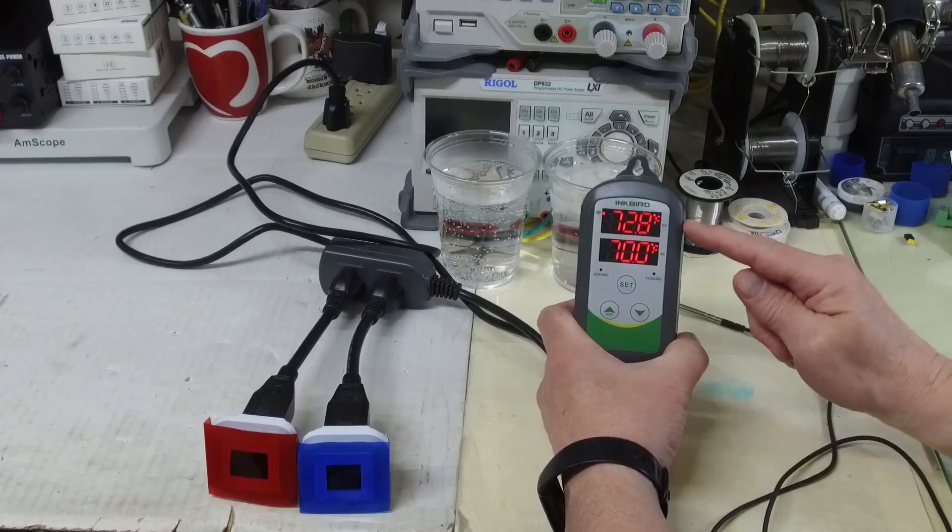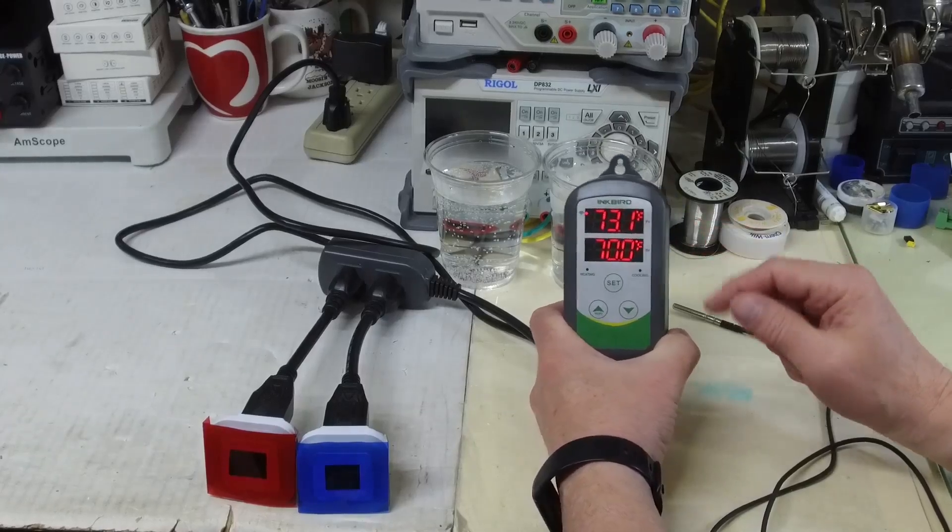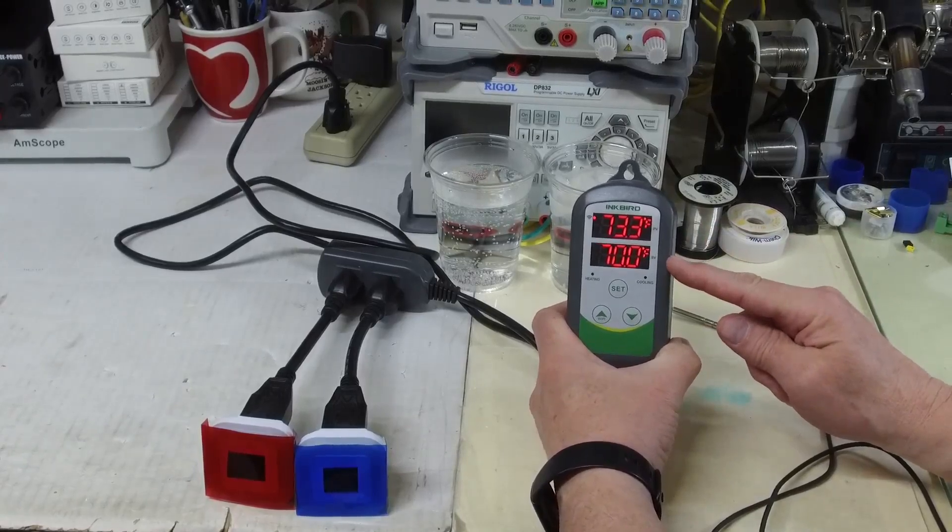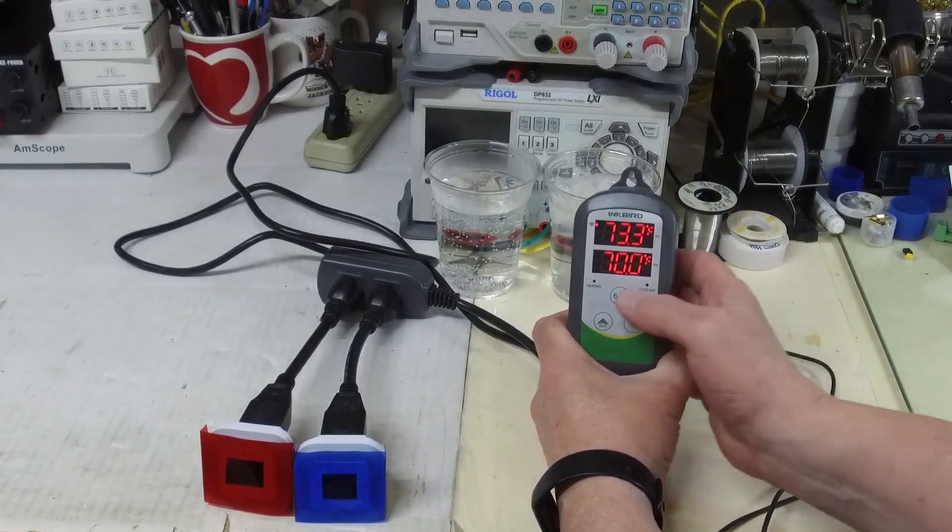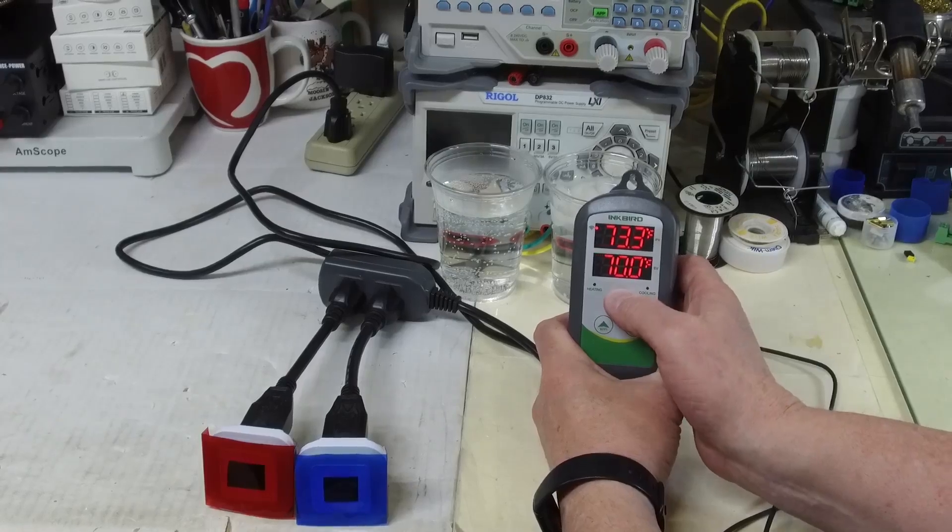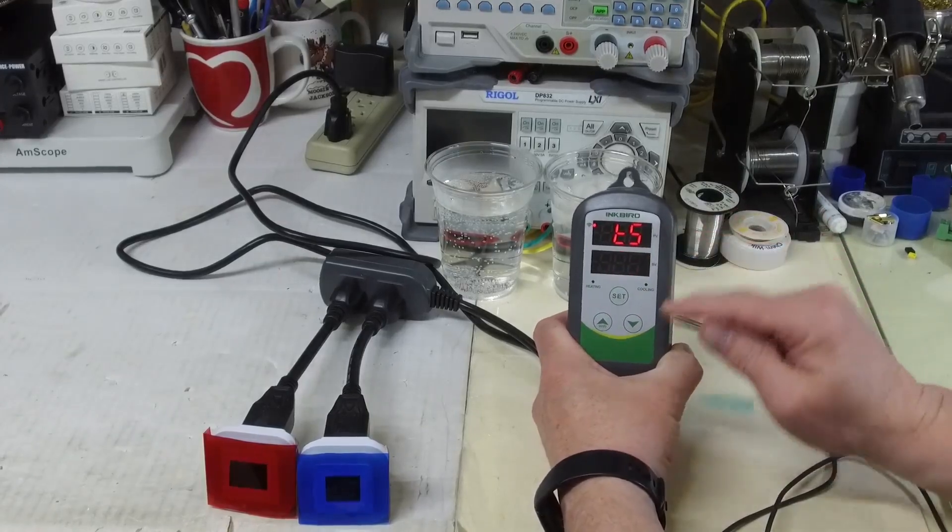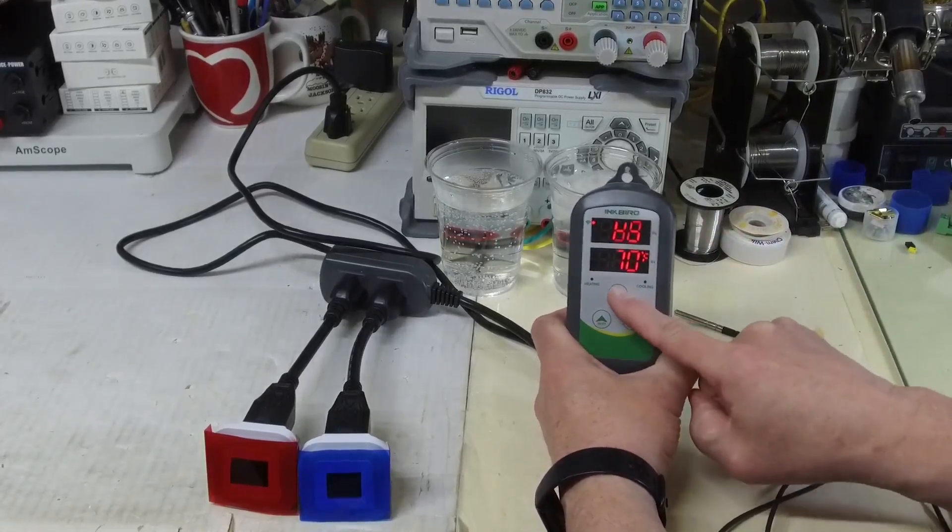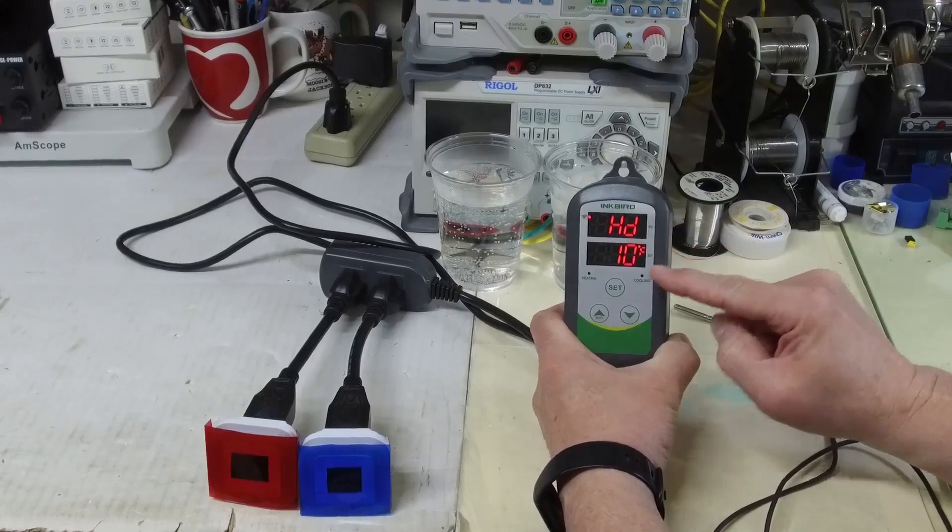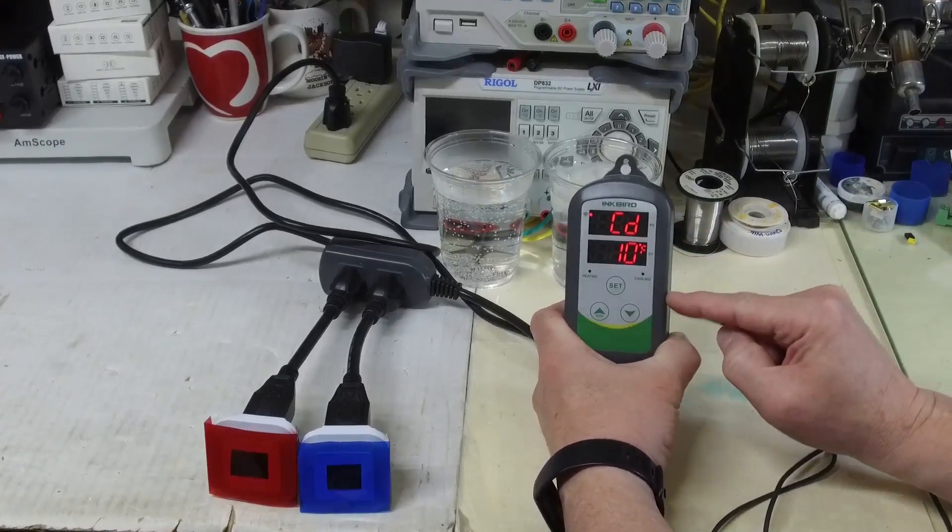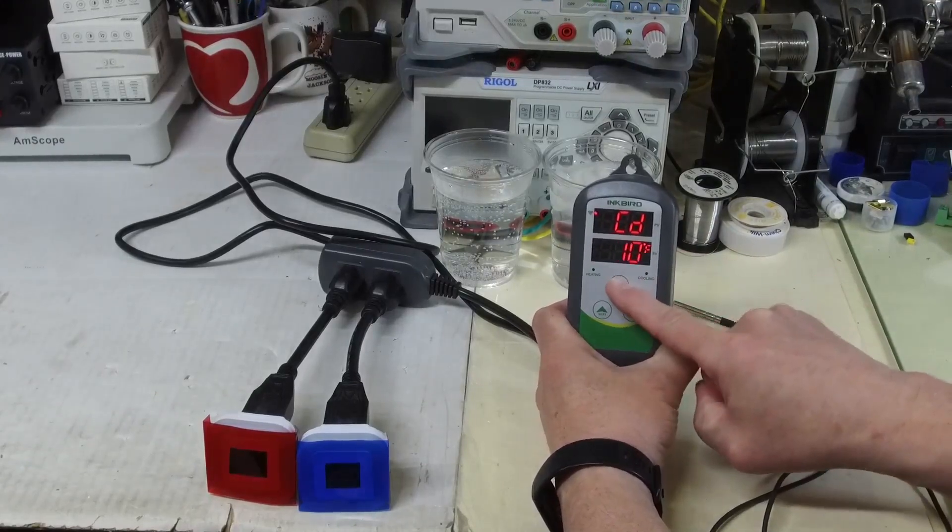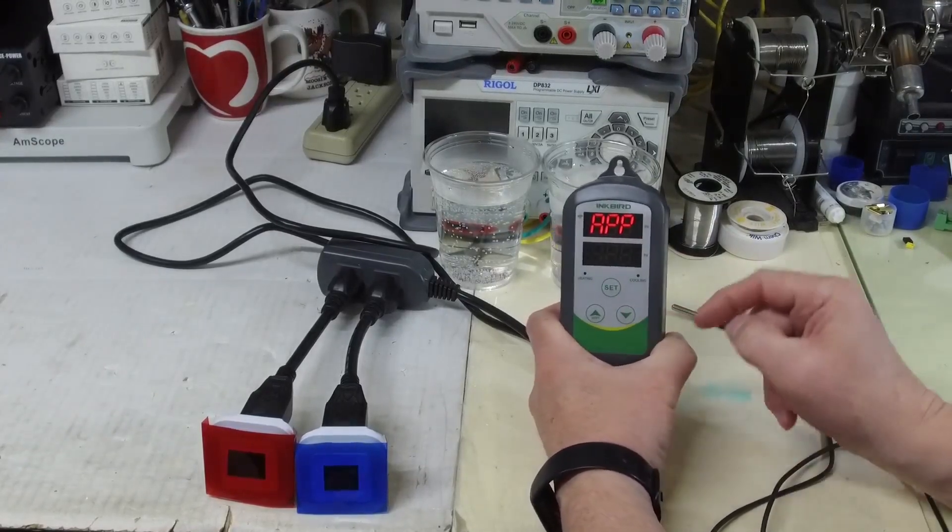Our current reading is roughly 73 degrees and our set value is 70 degrees. I can manually adjust the set points by pressing and holding this for three seconds. Here's our set point. I can adjust that up or down. Here's our heating differential—I'm going to keep that at 10. Here's our cooling differential—I'm also going to keep that at 10 right now. Press and hold for three seconds to exit.